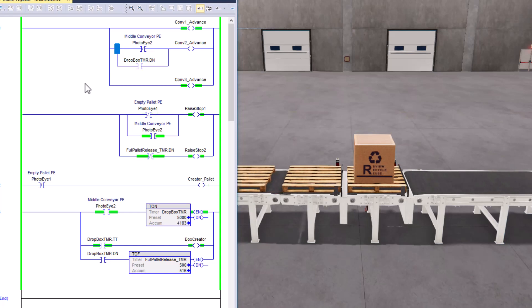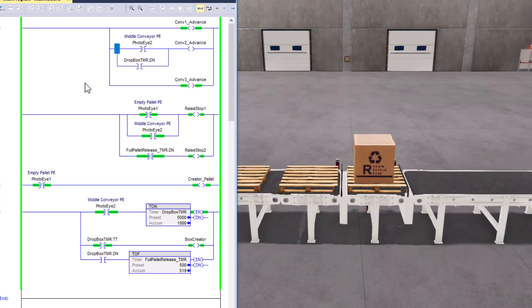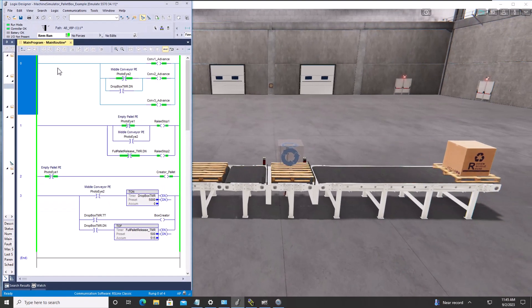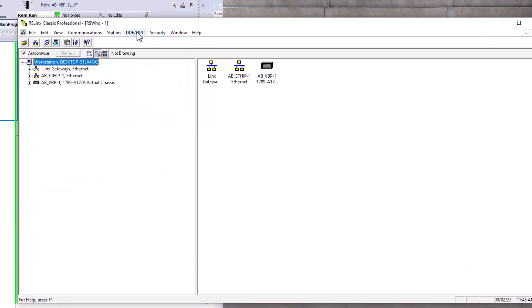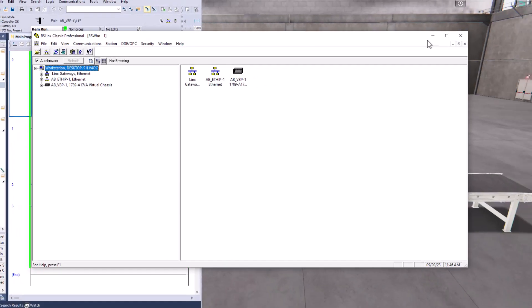Make sure the program does that scope of work continuously with no problem, and make it easy to read for whoever comes behind you to troubleshoot — because photo eyes fail, conveyors break, and things trip out. This is using RSLogix 5000 version 34, tied into an OPC topic through RSLinx Classic. Note: OPC topics do not work with RSLinx Lite — you need the licensed version. Hopefully you learned a lot from this video.